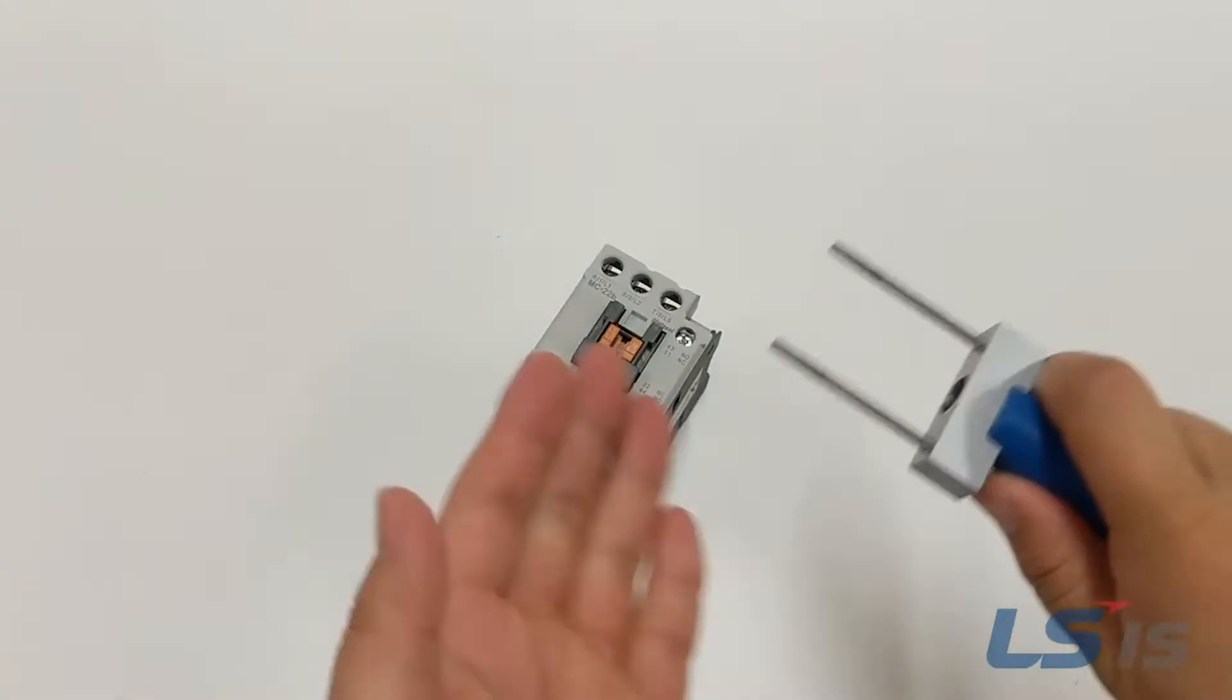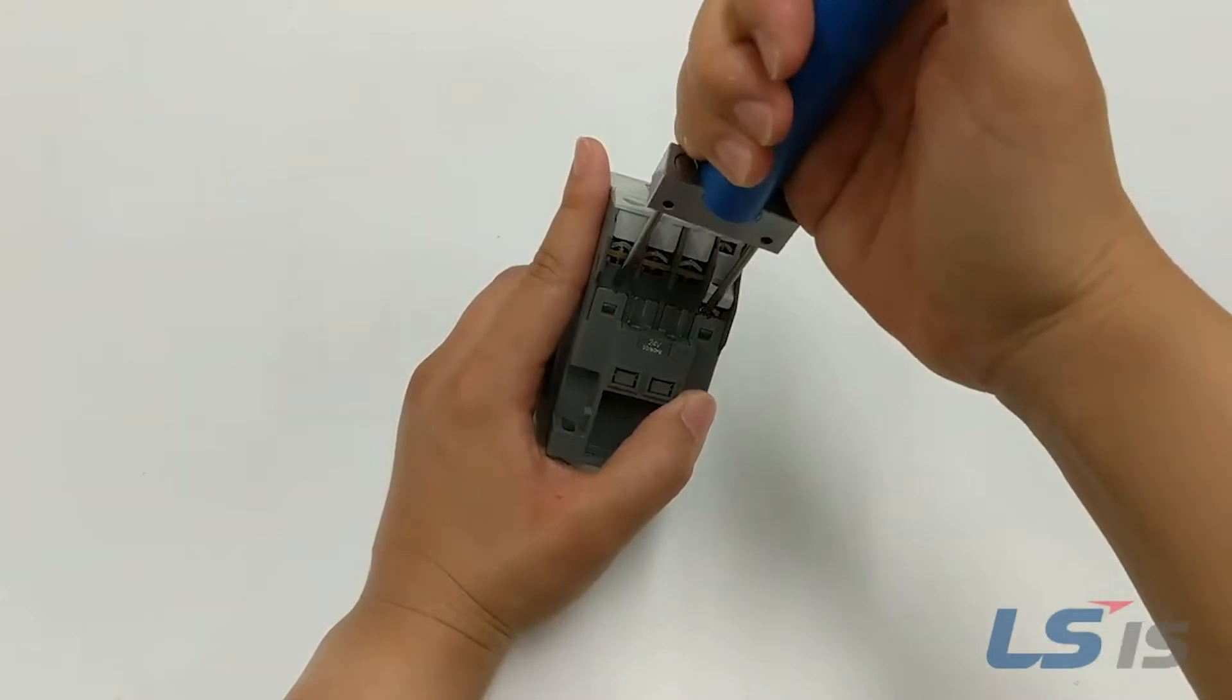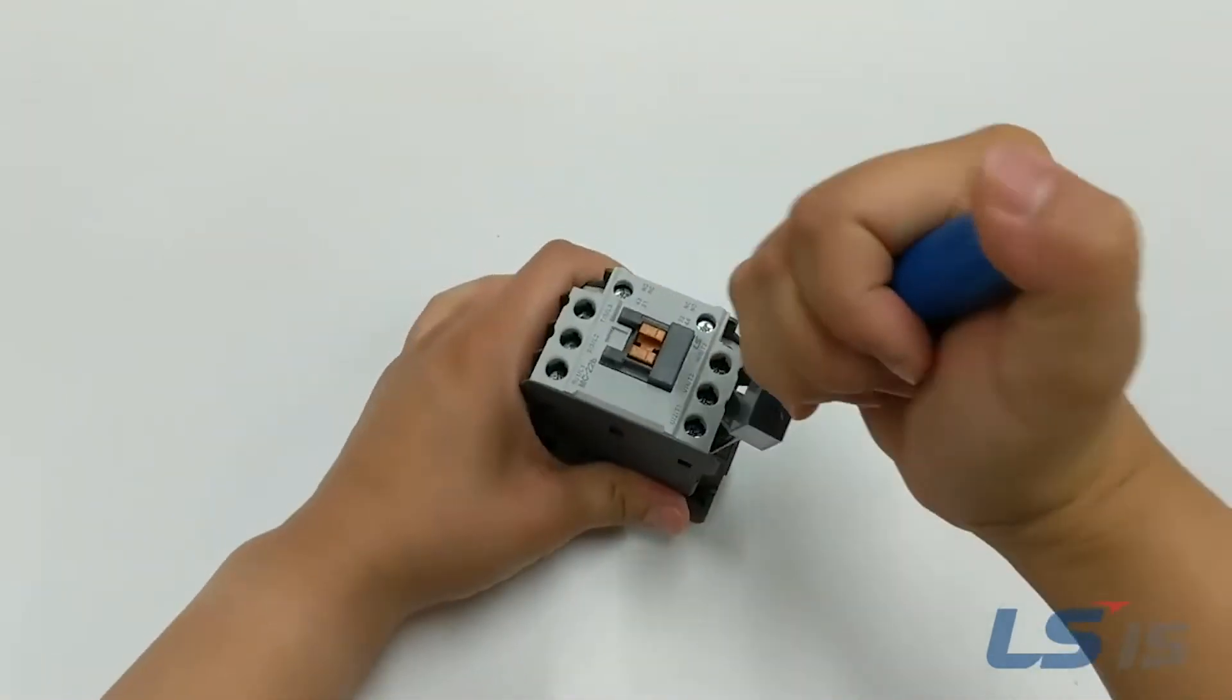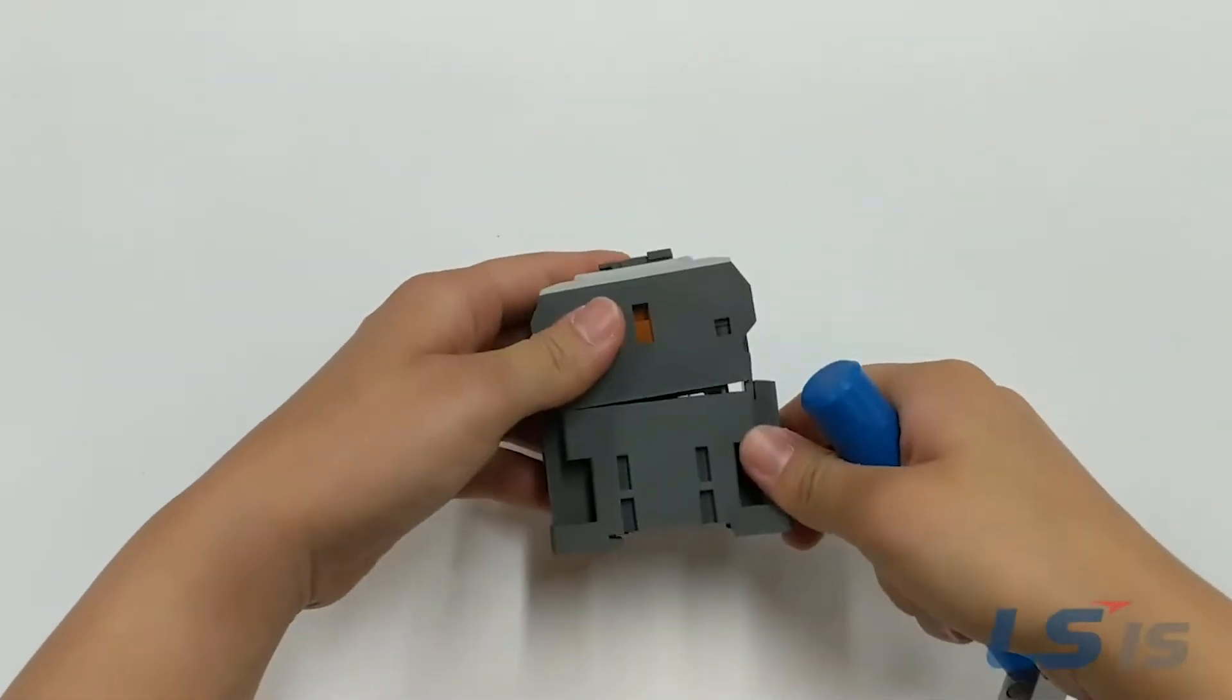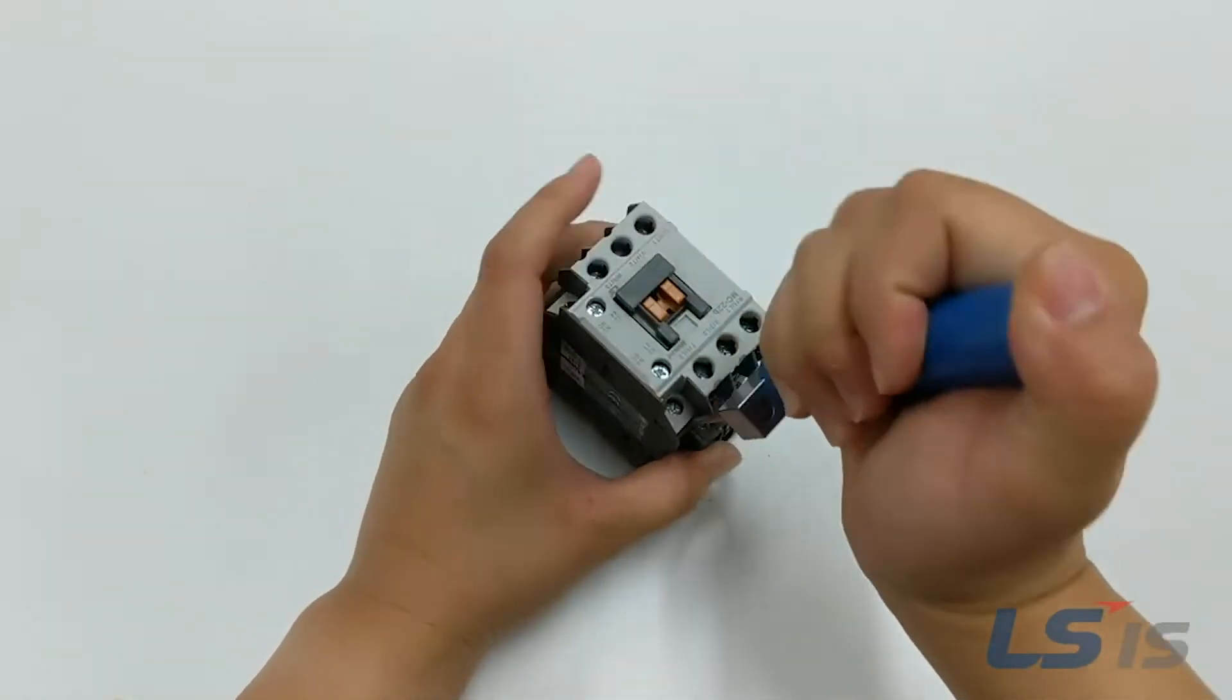Using your LSIS contactor tool or a flathead screwdriver, insert the blades into the outer plastic tabs and pull toward the body of the contactor in order to separate the tabs from the top. Repeat on the other side to fully separate the bottom half from the top half.